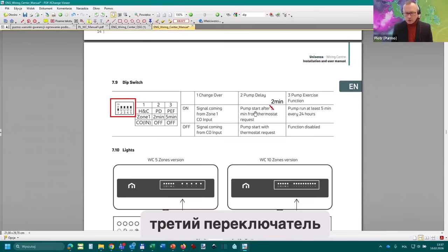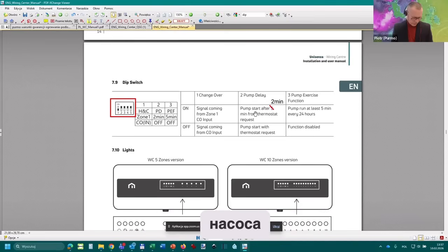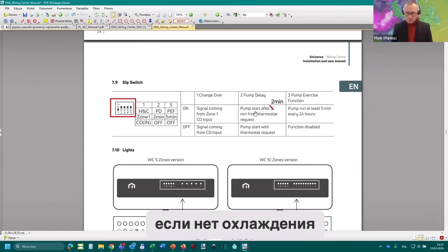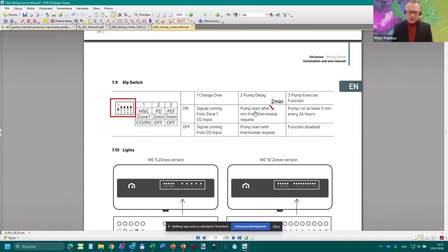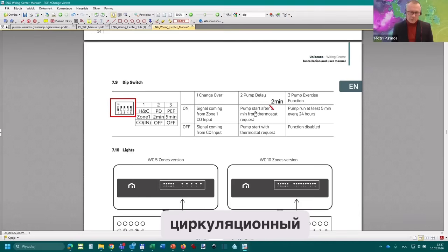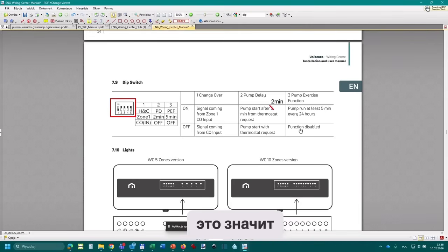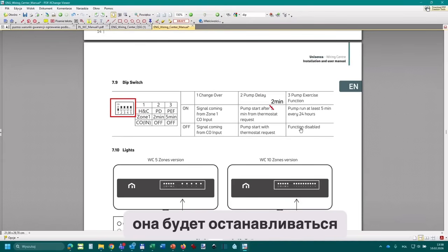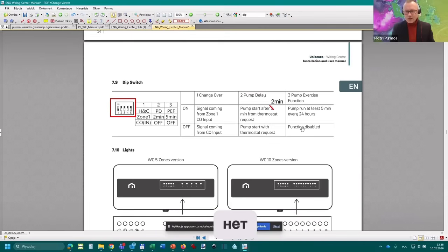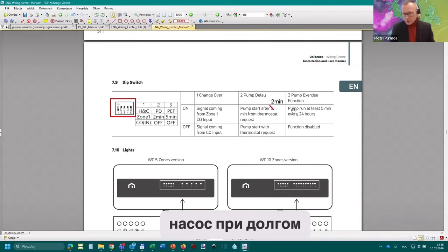Okay, and the third switch is pump exercise. In the summertime, if there is no cooling, the operation of the circulation pump stops. If the water is dirty, the circulation pump can be blocked. Therefore, there is a function to switch it on for 5 minutes every 24 hours, or switch off this function. So the third one controls pump regulation in the summertime, to not block the pump during a long time of non-operation.